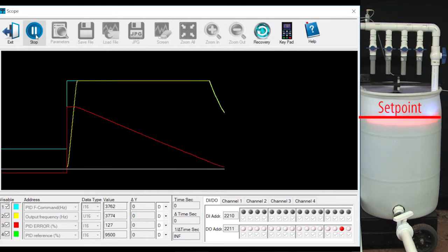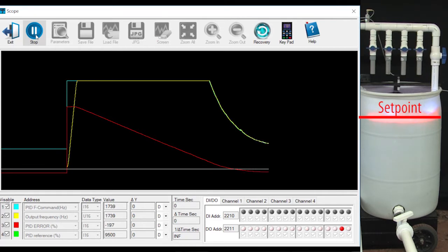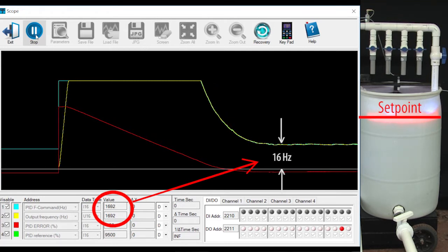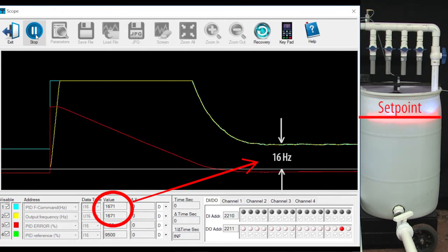The error gets smaller and smaller as the water level approaches the set point. And as the water level starts to get close to the set point, PID automatically slows the motor down. Looks like our demo needs to maintain the output frequency at around 16 Hz to maintain the water level at the set point for the particular demand I created by opening that drain valve a little bit.